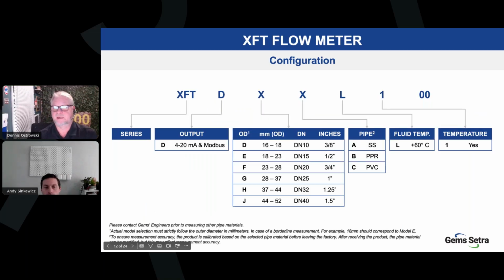Okay, how to configure the device. First of all, it's an XFT. We all know that. The first option is not an option. You automatically get the Modbus along with the 4 to 20 milliamp output, so that's all included with your first option. Then you're picking your pipe diameter: 3/8, 1/2, 3/4, 1 inch, 1 1/4, and 1.5 inches are the choices there. The pipe material: stainless steel, PPR or PVC are available. And then your next options are forced options of the fluid temperature, and you always get the temperature readout. So those are the ways that you can configure this product.